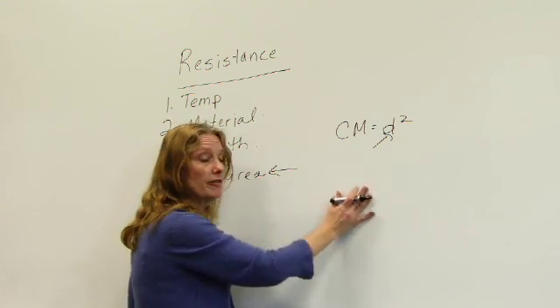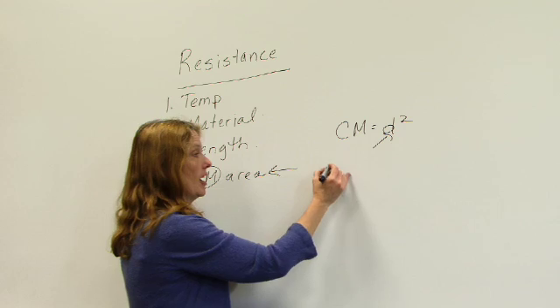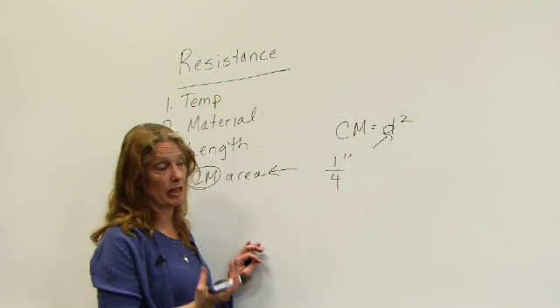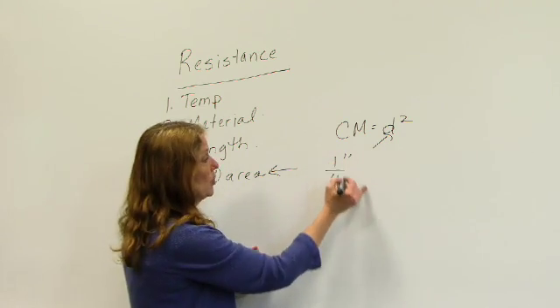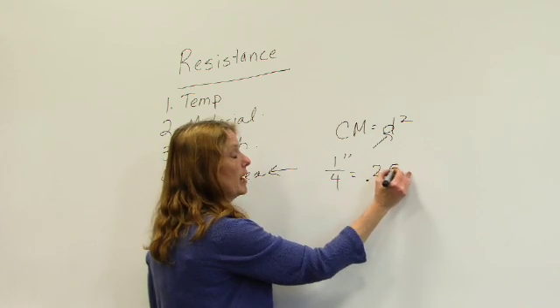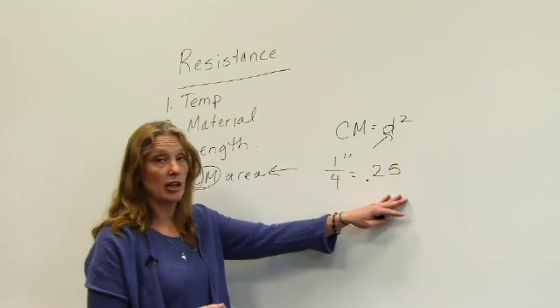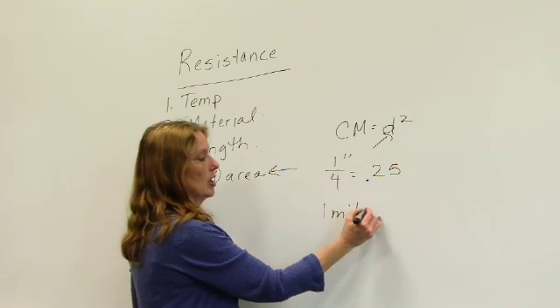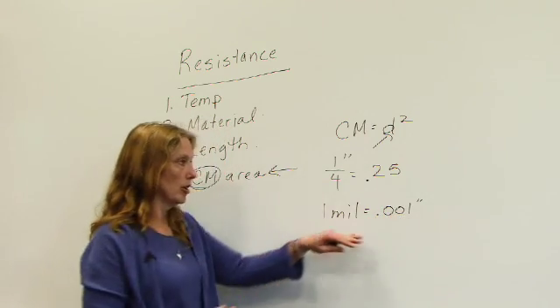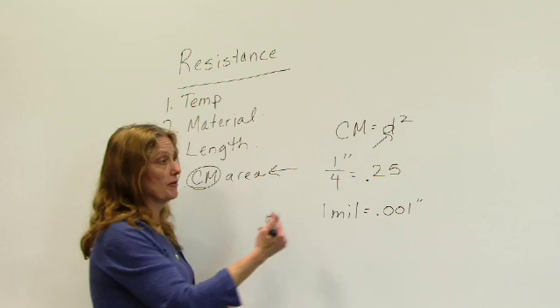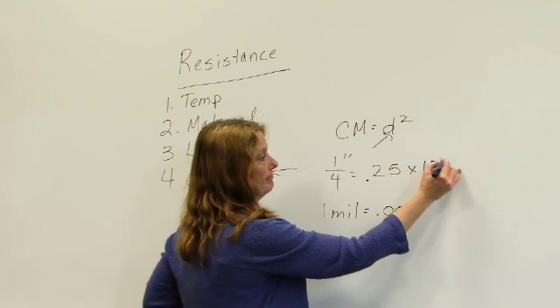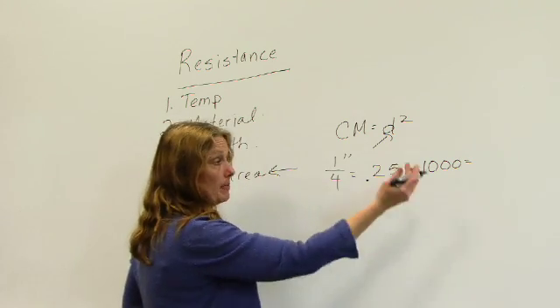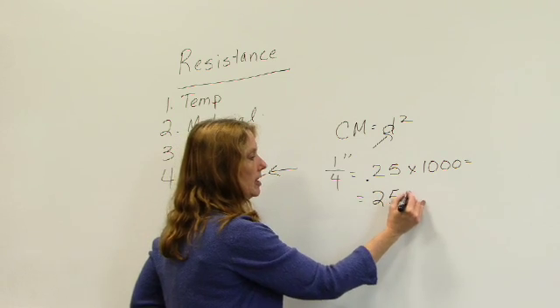So what we would do is if I have a quarter inch diameter conductor, I would first need to change this quarter inch, which is real common here in the U.S., and change it to a decimal. So I take one divided by four, come up with 0.25. The next thing is I want to convert it to mils. To convert from inches to mils, I multiply it by 1,000. Taking 0.25 times 1,000, I come up with 250 mils.